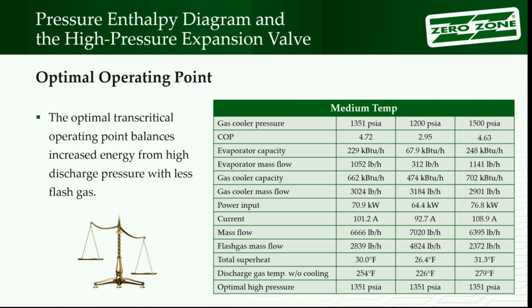Up, up, up, up, up. You're going to keep wondering why I can't maintain my suction pressure on my high stage compressors. You're going to be generating flash gas, they're still ripping along flat out, and the pressure just keeps going up. The lower you make the head pressure, the higher the suction pressure goes. So that's what you'd see, because the evaporator doesn't know to say, let's stop doing so much cooling and let the flash gas do all the work. You're just going to have more gas, and it means higher suction pressures, and you'll lose capacity that way.